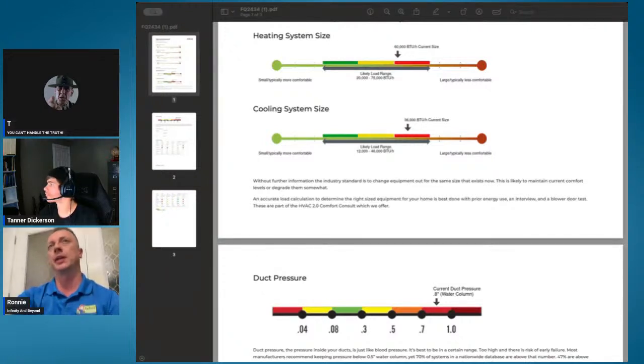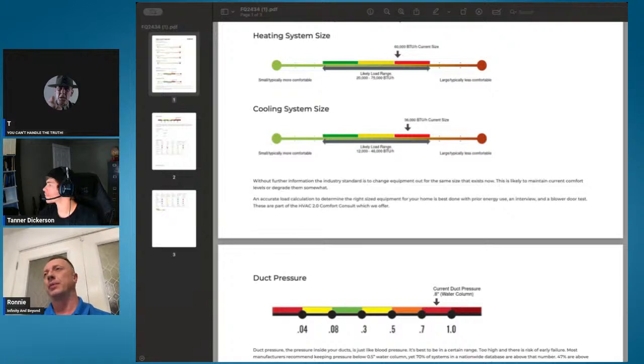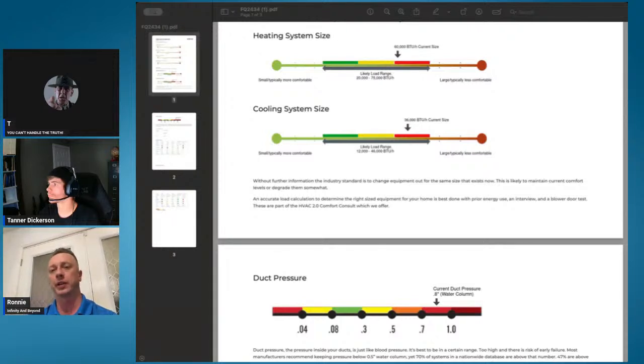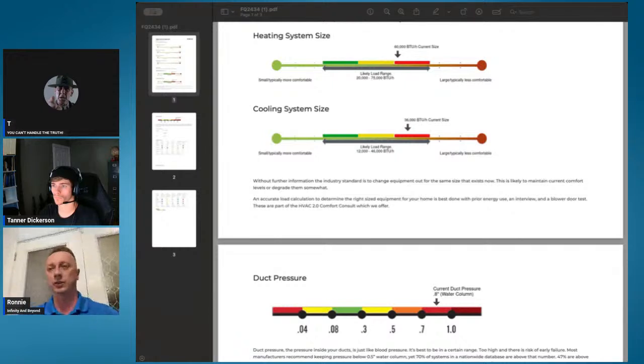A little bit of that would be like, usually I have a bit more ammunition, like if we have duct pressure stuff, where I can basically say, with this old system PSC motor with a 1-inch water column, you're probably not performing at 5-ton capacity. We could actually, now that I have the True Flow grid, see what CFM they're actually running at. So say it's a 5-ton system operating at 1200 CFM, I just have to show them a way to understand what that means, and based on tonnage, what CFM or tonnage of cooling they're actually getting.